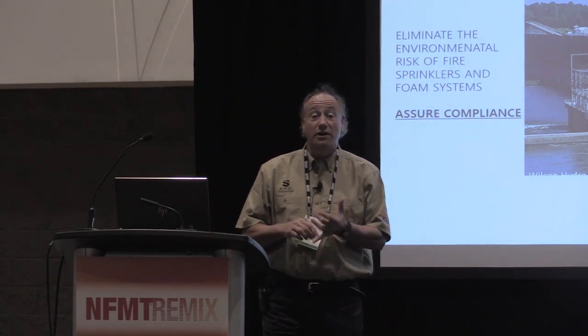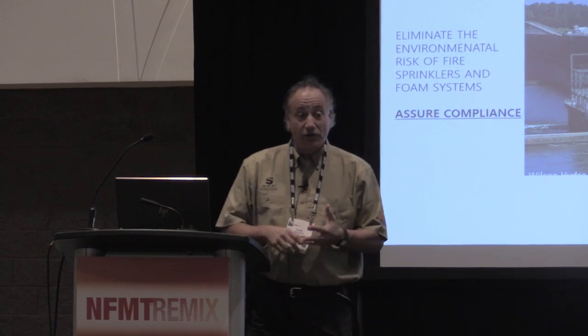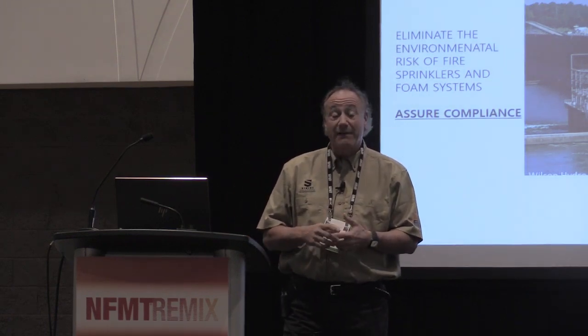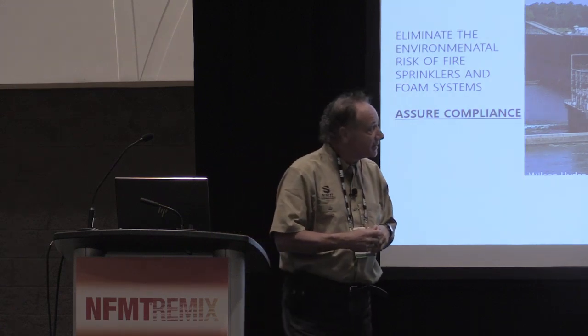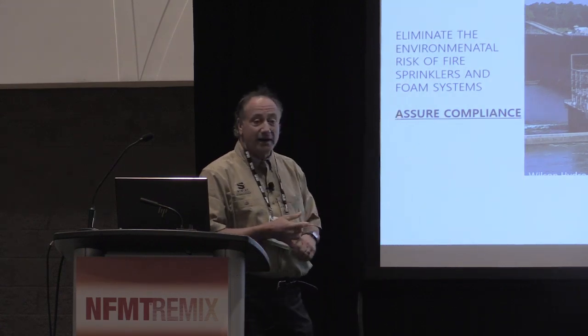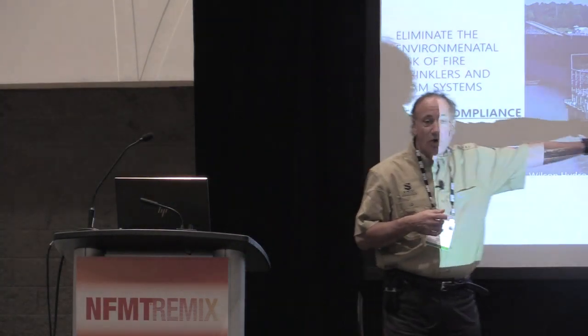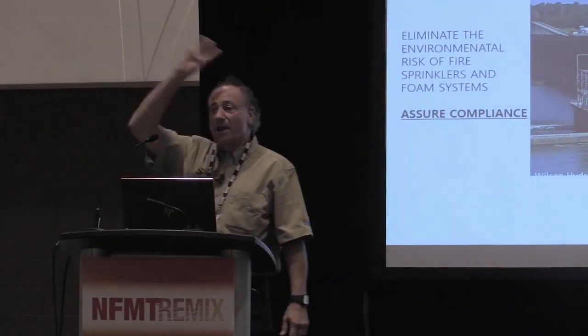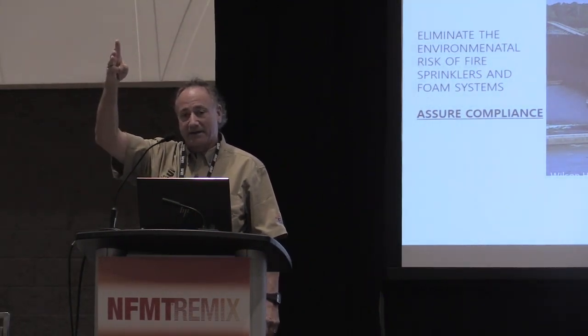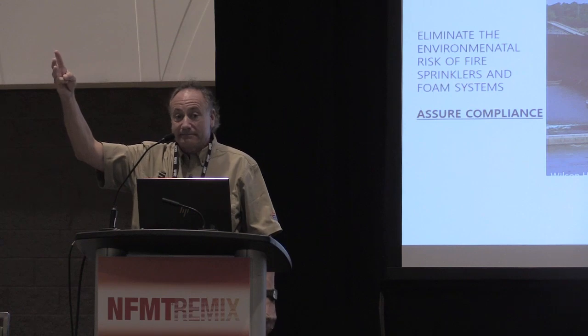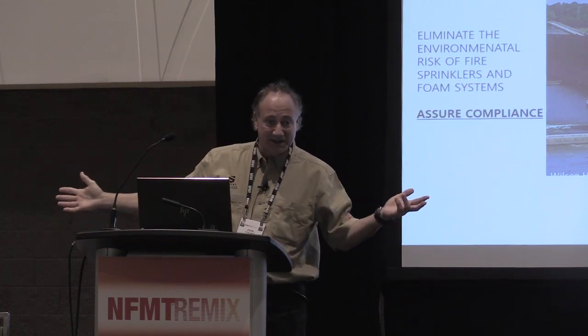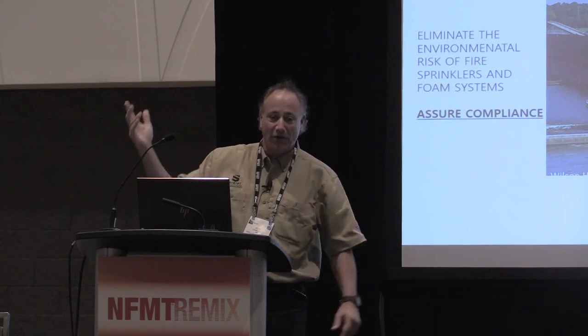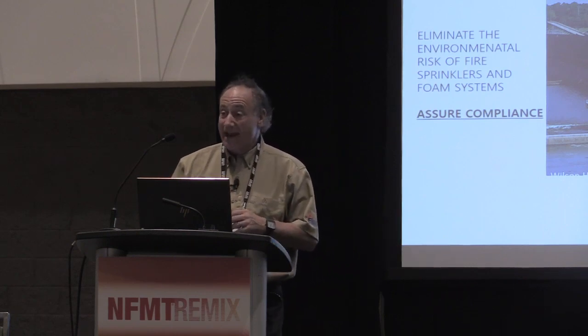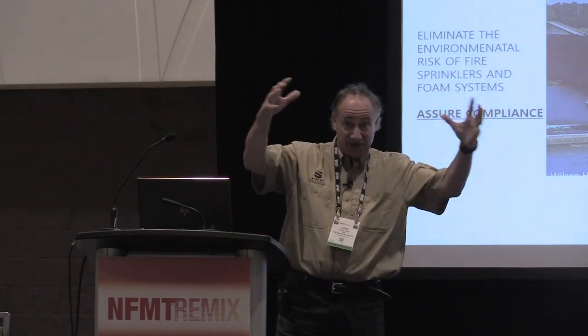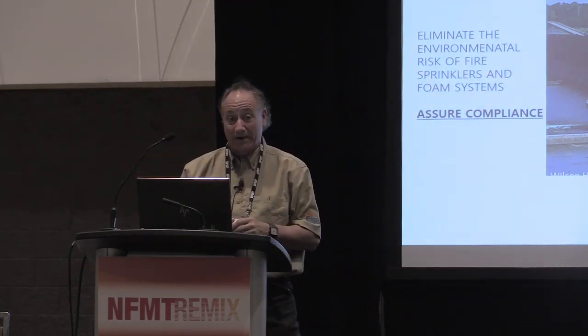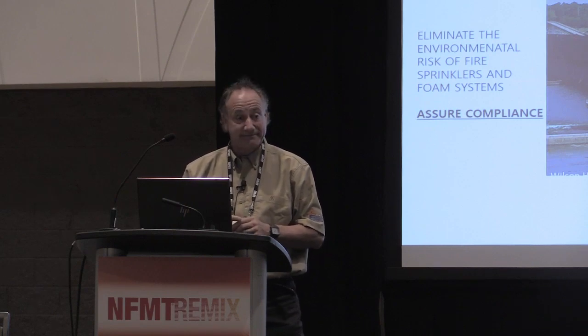Environmental insurance, if you guys are near, and ladies are near waterways, creeks, lakes, if you have a sprinkler system on your transformers, not going to do well for you. We do a lot of work around transformers and waterways. There's 3 methods for compliance for transformer fire barriers, all right? You could use foam. Foam is outlawed. It's a carcinogen. The firefighters are suing all of the foam manufacturers now, and foam systems are coming out of facilities. Typically, you remember the big shaving cream foam, AFFF, aqueous film forming foam, no longer can be used.